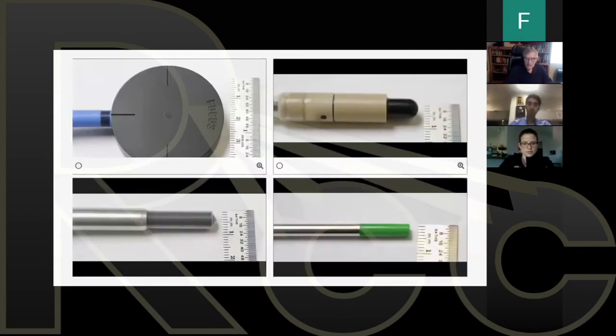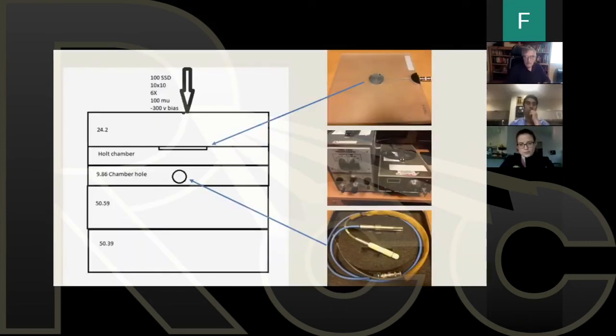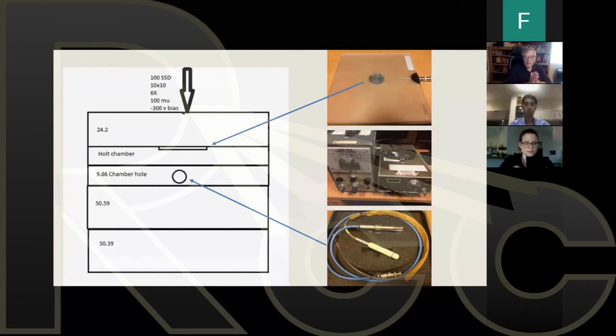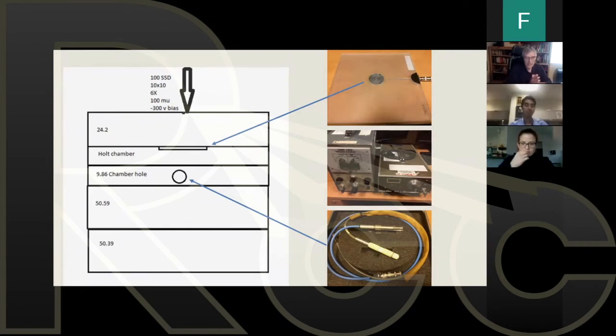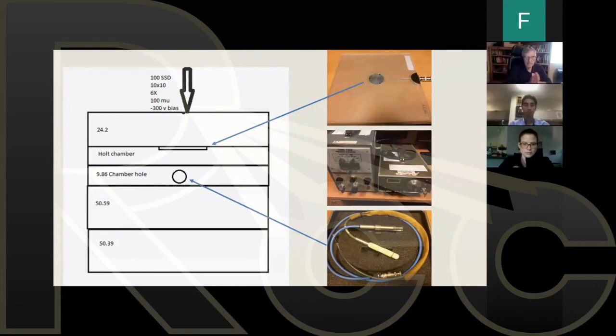As you know, we use a variety of chambers in our practice. These are just some of the ones we use. Chambers, thimble chambers, scanning chambers, parallel plate chambers, even diode dosimeters are used for certain measurements. In my center, I do not have a large group of physicists. Many times I practice alone. Presents unique problems because who is checking me? Well, of course, I have the TLDs that are sent in semi-annually to make sure that my machines are calibrated correctly. That is so reassuring when you get that report back saying, yes, your beams are calibrated correctly. I can't emphasize how important that yearly or semi-annual validation of your output is by an outside agency.